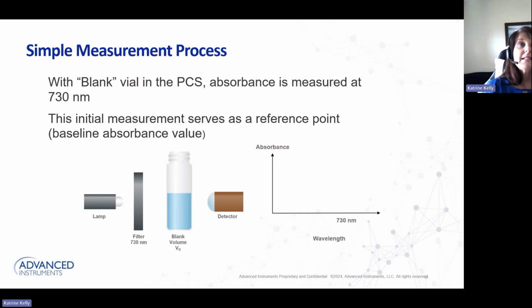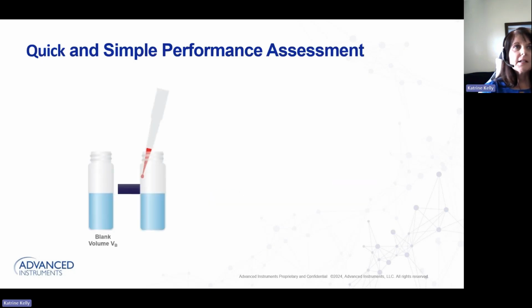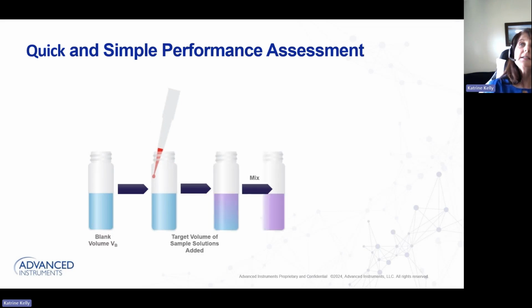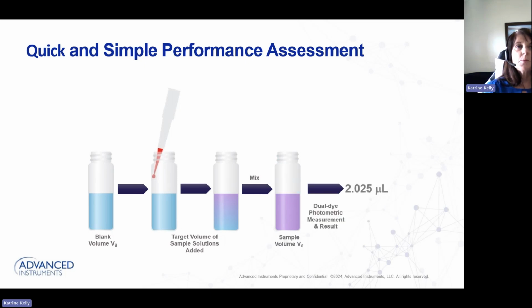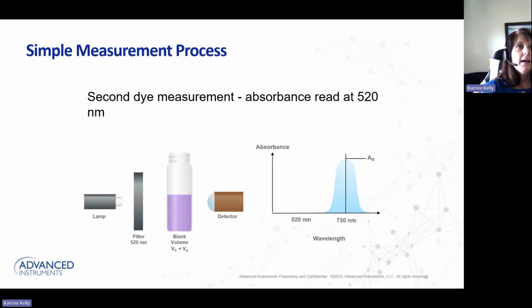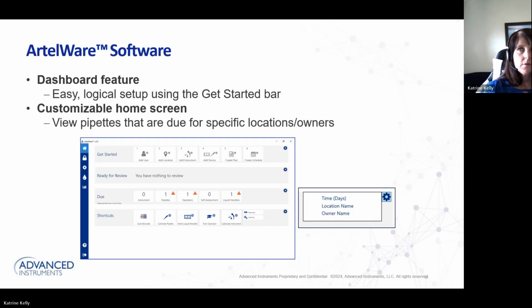So operation of the PCS is designed to be very simple. You insert a blank vial into the PCS instrument, close the lid, and the PCS then takes an initial absorption reading at 730 nanometers. Next, you pipette the QualiSure solution or the red dye into the blank vial and close the lid, and then the PCS will mix the two solutions together. It has a vortex mixer. And then finally, the instrument takes a second reading at 520 nanometers and provides you with the absorption difference or the results. And those calculations are completed automatically for you.